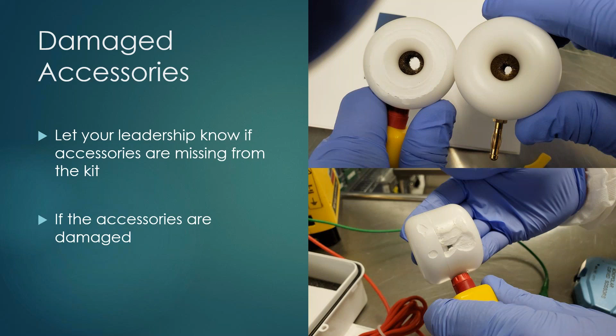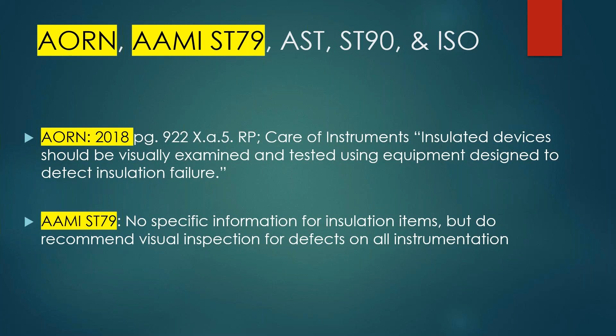So we kind of went over how to buy one, what to look for in the accessories, but who says how or whether I should be testing? So let's start with AORN. AORN in 2018, in their statement on care of instruments, says insulated devices should be visually examined and tested using equipment designed to detect insulation failures. AAMI ST79 says there's actually no specific information on insulated items at this time, but does recommend visual inspection for defects of all instrumentation and devices.